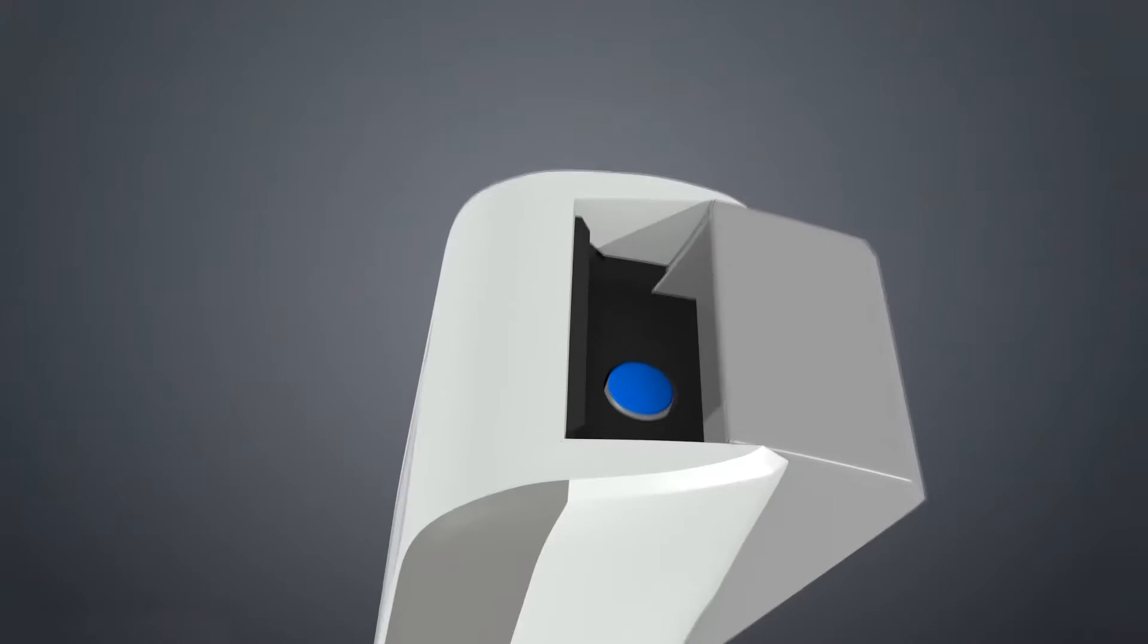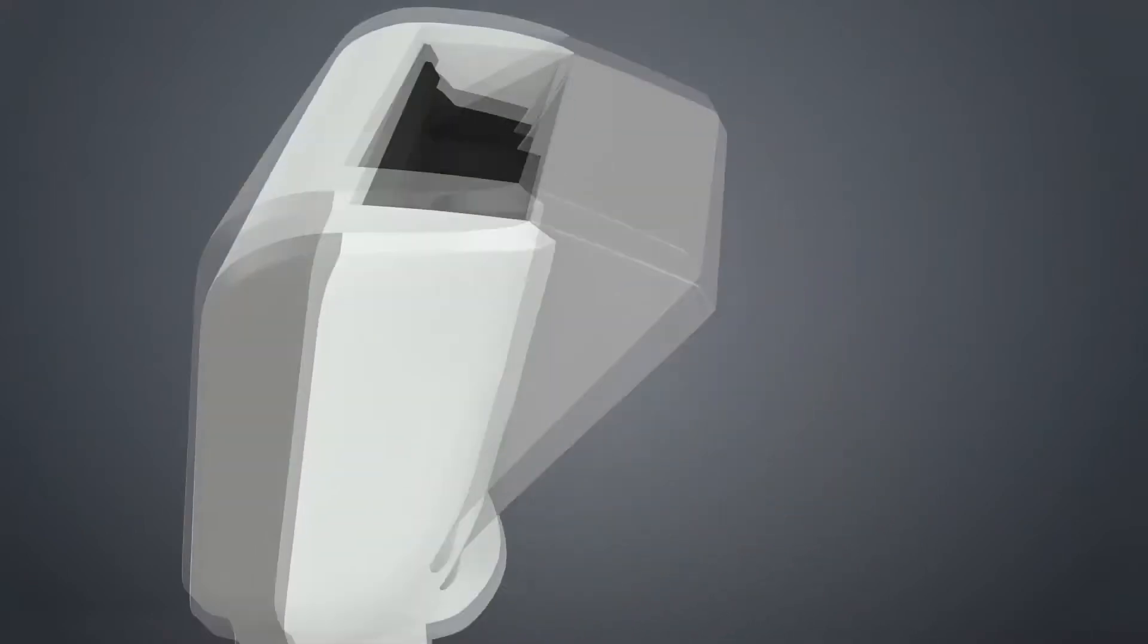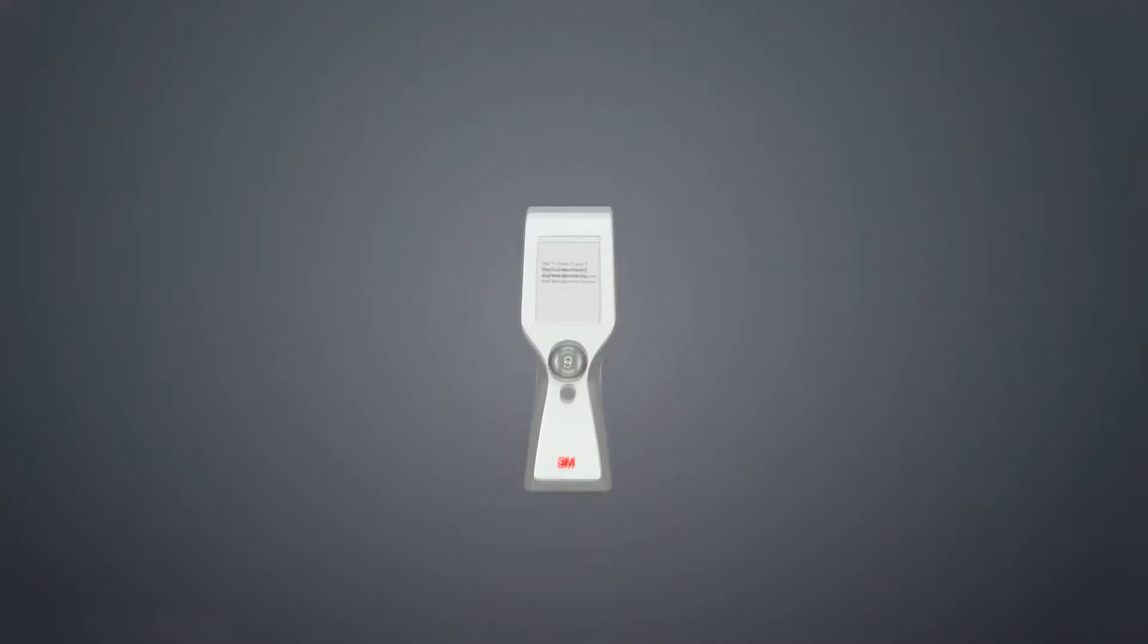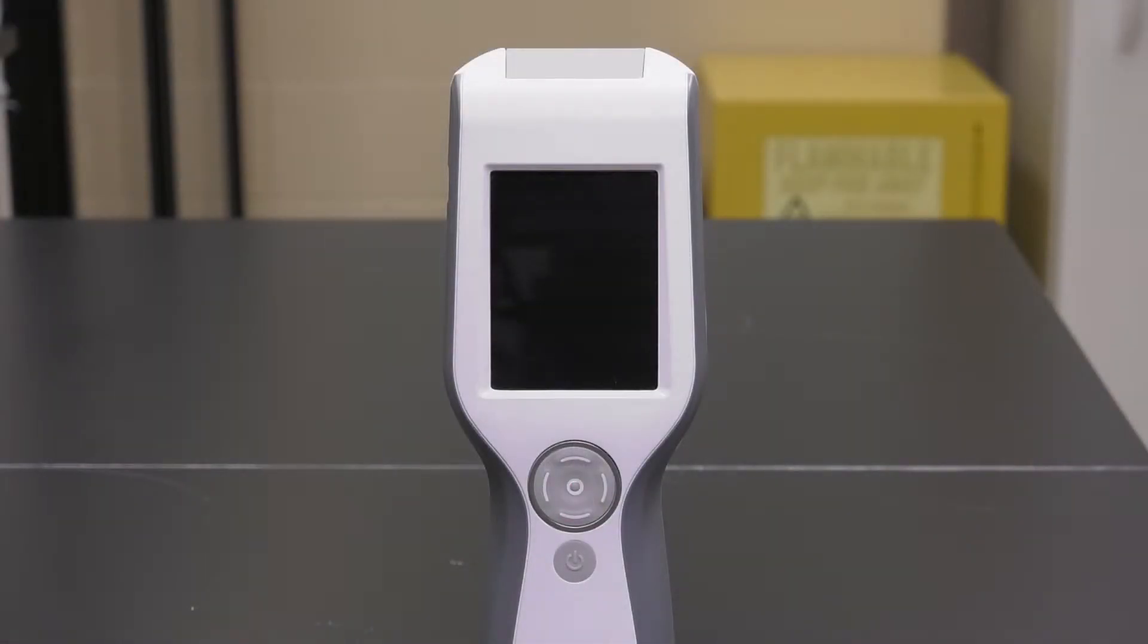Before switching on the 3M Cleantrace luminometer, check the test chamber to make sure it's empty. It is highly recommended not to leave used swabs in the chamber after use. Leaving used swabs in the chamber may damage the equipment.